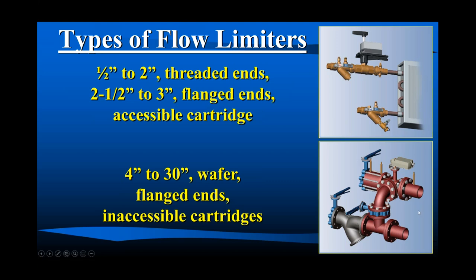Yes, it would, because it doesn't see the pressure drop of the coil any longer. It's got a home run right back. So if this was a manual valve, fixed orifice, right, with the same pressure, it would overflow. An overflow costs somebody money. So if this is a manual balance valve system, you would have to add another manual balancing valve in this bypass to mimic the pressure drop of the coil.